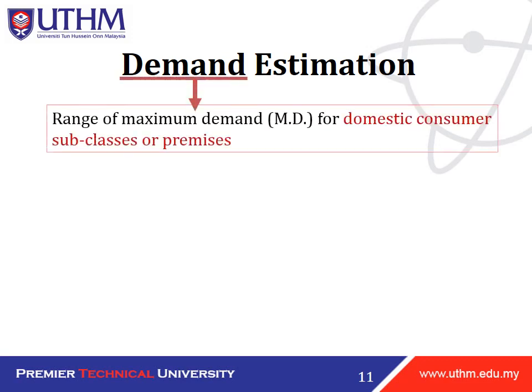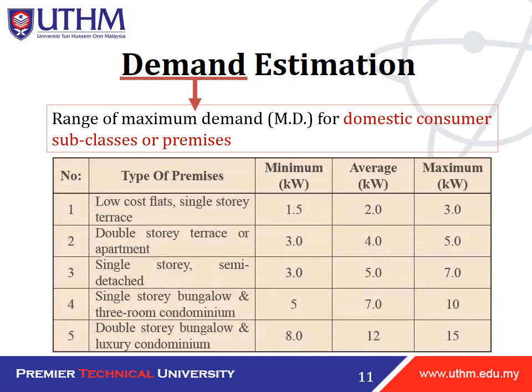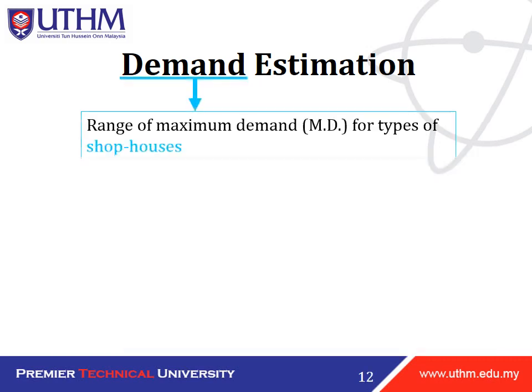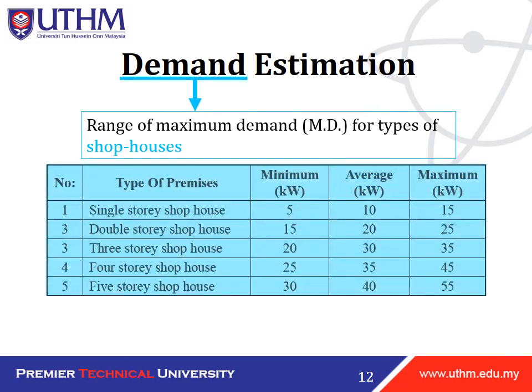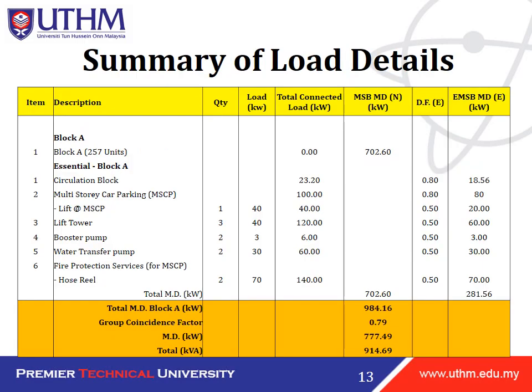Okay, now we go to the demand estimation. So the range of maximum demand for domestic consumer subclasses or premises is as depicted on the table. So we can see a lot of types of premises with different minimum and maximum kilowatt demand. And then the range of maximum demand for types of shop houses is as follows. So we have single story, double story, 3-story, 4-story, 5-story shop house with different values of minimum, average and maximum demand.